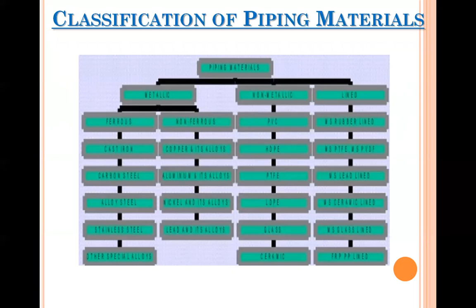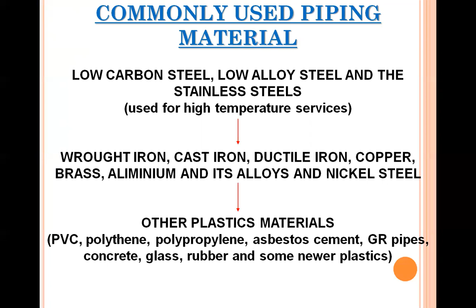The commonly used piping materials in general applications, in steam applications, in boiler applications, or in process industries are low carbon steel, low alloy steel, and stainless steels. These are used for high temperature services. Then wrought iron, cast iron, ductile iron, copper, brass, aluminum and its alloys, and nickel steel. Then other plastic materials, as I explained, are PVC, polyethylene, polypropylene, asbestos cement, GRP pipes, concrete, glass, rubber, and some newer plastics. These are the commonly used piping materials.